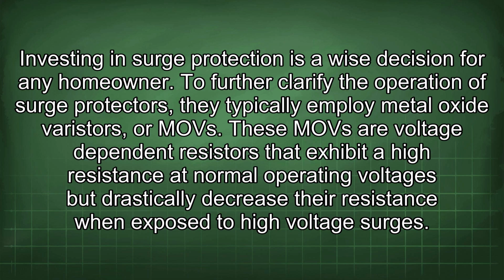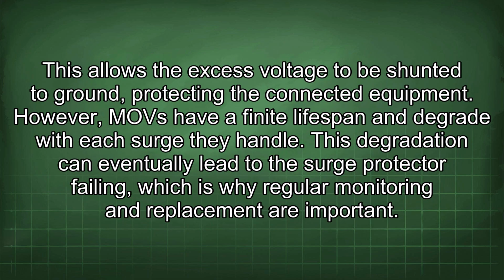To further clarify the operation of surge protectors, they typically employ metal oxide varistors, or MOVs. These MOVs are voltage-dependent resistors that exhibit a high resistance at normal operating voltages but drastically decrease their resistance when exposed to high voltage surges. This allows the excess voltage to be shunted to ground, protecting the connected equipment. However, MOVs have a finite lifespan and degrade with each surge they handle. This degradation can eventually lead to the surge protector failing, which is why regular monitoring and replacement are important.